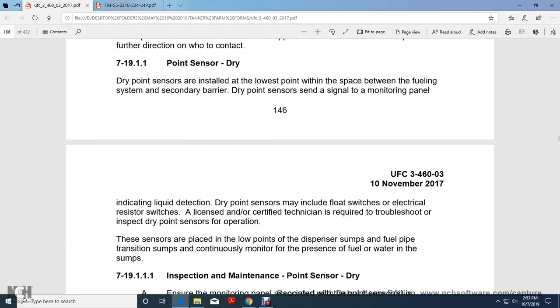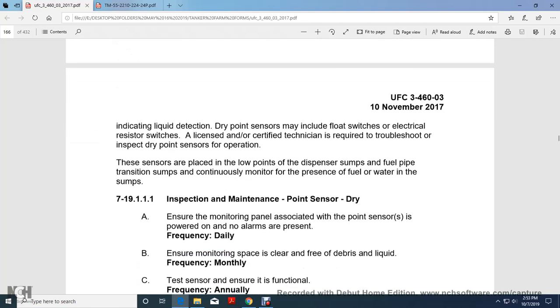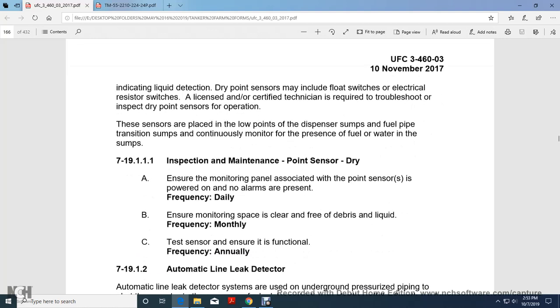Point sensor dry sensors are installed at the lowest point in the space between the fueling system secondary barrier. The dry sensors send a signal to the monitoring panel indicating liquid detection. Dry point sensors may include float switches and electrical resistor switches. A licensed certified technician is required to troubleshoot and inspect dry point sensors for operation. These sensors are placed in low points of the system, such as dispenser pans, fuel pipe points, and transition sumps, continuously monitoring the presence of fuel or water in the sumps.